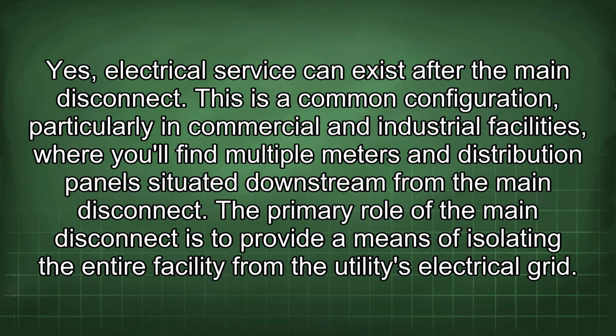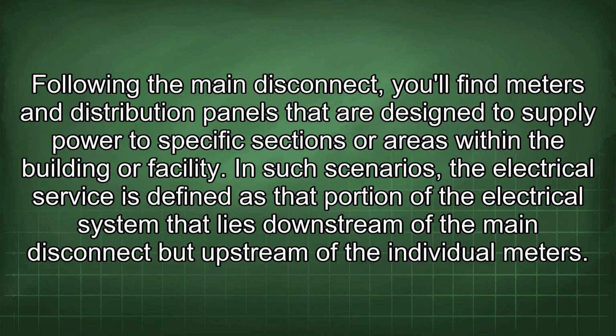Yes, electrical service can exist after the main disconnect. This is a common configuration, particularly in commercial and industrial facilities, where you'll find multiple meters and distribution panels situated downstream from the main disconnect. The primary role of the main disconnect is to provide a means of isolating the entire facility from the utility's electrical grid. Following the main disconnect, you'll find meters and distribution panels that are designed to supply power to specific sections or areas within the building or facility.